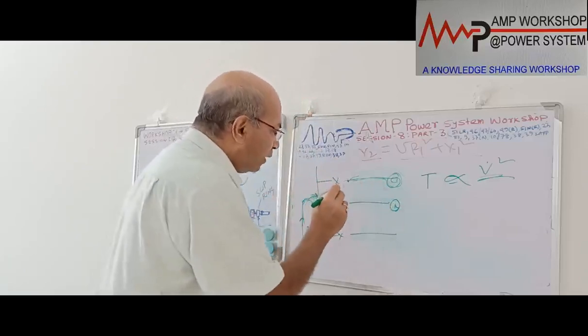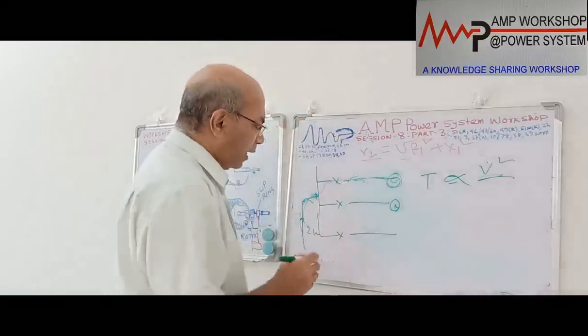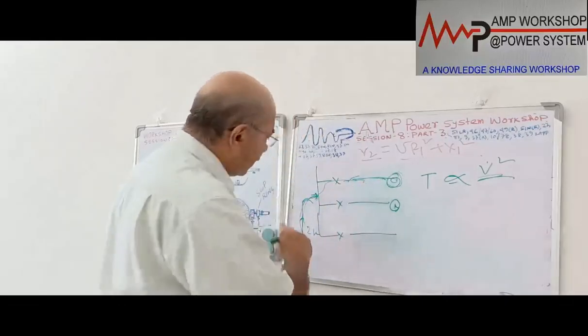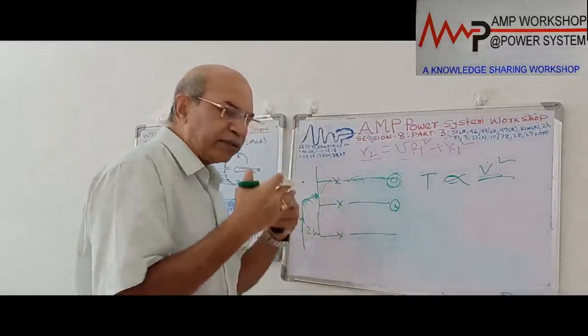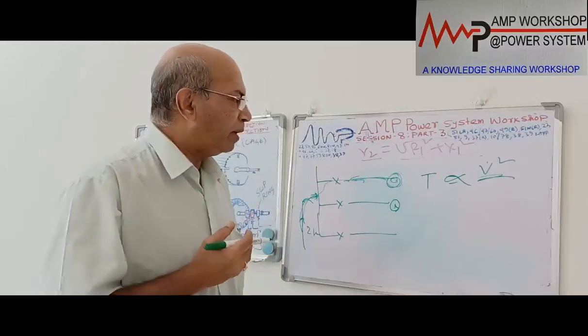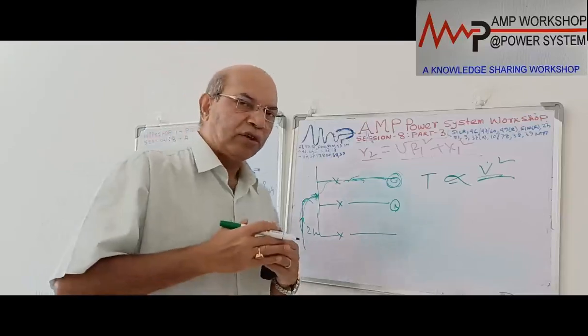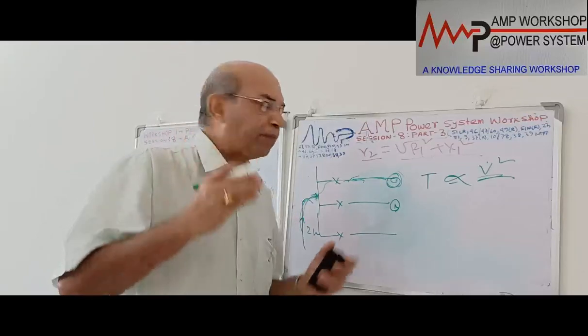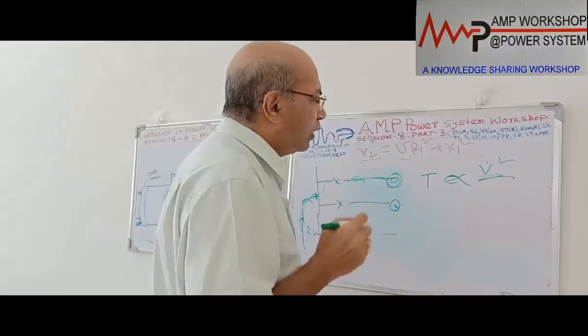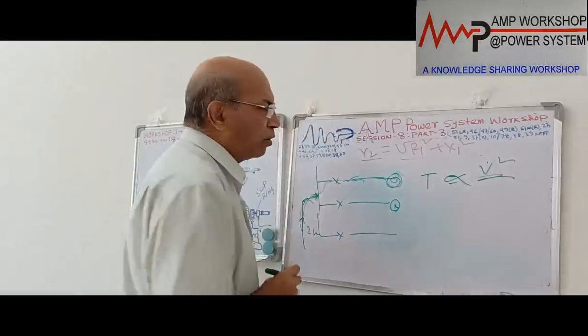on the terminals. And on this voltage, the input voltage is injected again after 100 milliseconds, when the voltage has not fully decayed. At that time the supply voltage comes up, and these two voltages may not be in the same phase. It may be in opposite phase. If it is in opposite phase, up to 2 times the voltage may come on the motor, and then the motor will burn out. Motor insulation will fail. So that type of scenario can also take place.